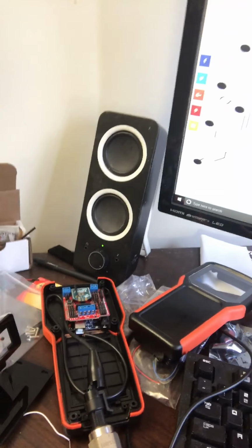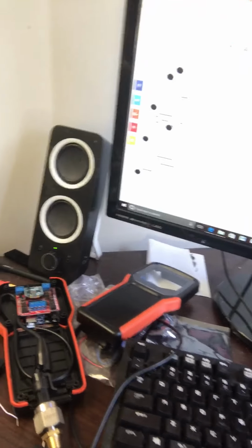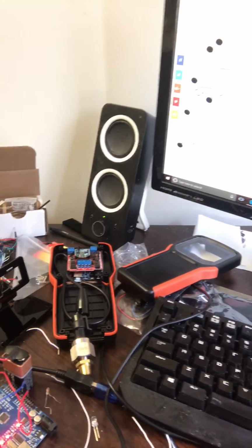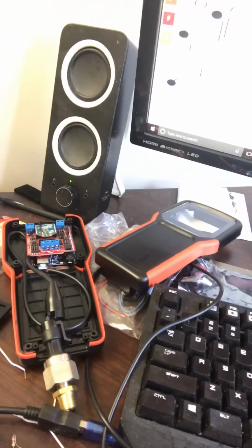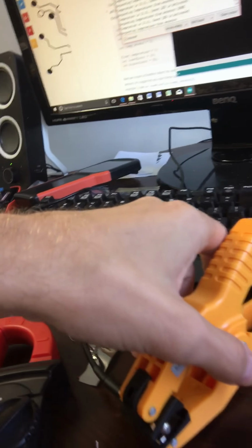I'll use all sorts of mathematical formulas to translate the R22 refrigerant in a residential system, to provide me with the proper subcooling and superheat information, all in real time. So this is going to be pretty cool. I'm gathering this temperature right now directly from this clamp, and I'm going to have two of those clamps as part of the device I'm building.